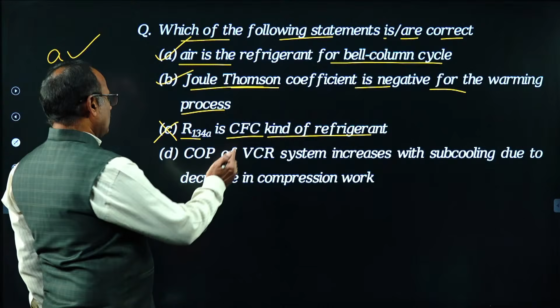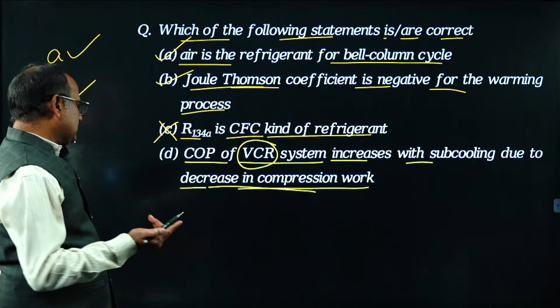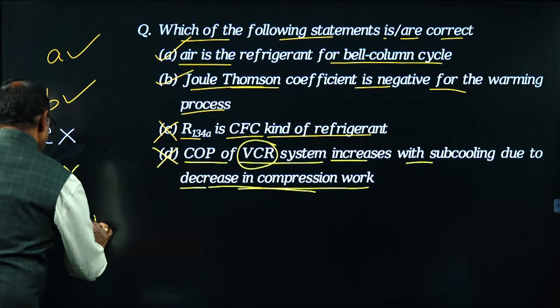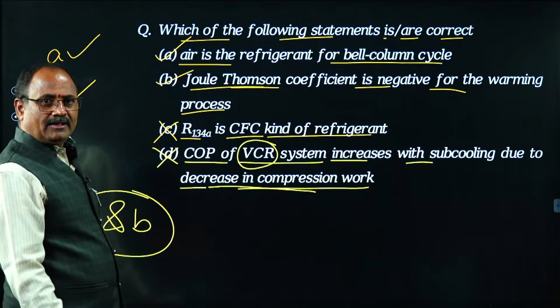COP of vapor compression system increases with subcooling due to decrease in compression work. Because of the subcooling in vapor compression refrigeration, VCR means vapor compression refrigeration, COP increases due to increase in refrigeration effect, not due to decrease in compression work. That is due to increase in refrigeration effect. Therefore, D is absolutely wrong. Therefore, A and B are correct. Are you following clearly? Yes.